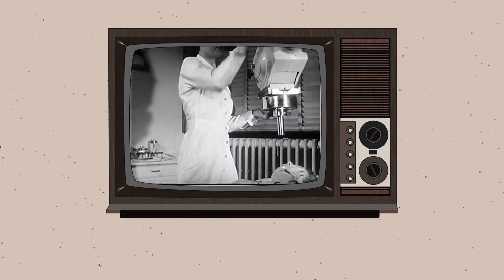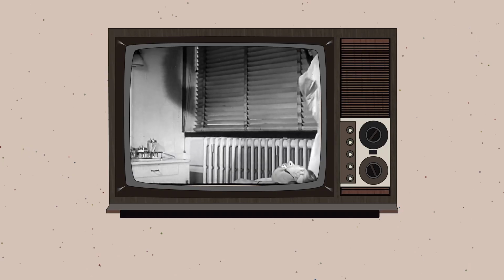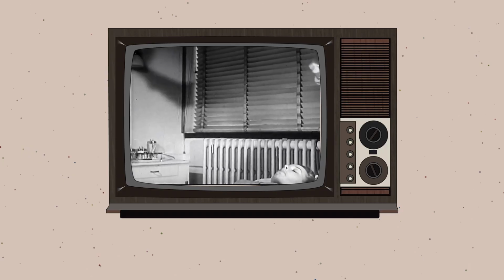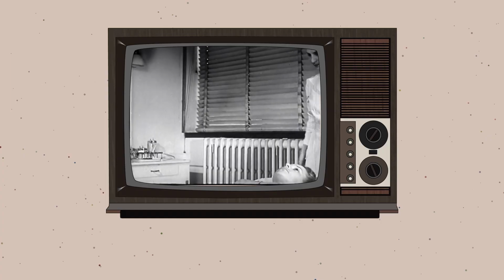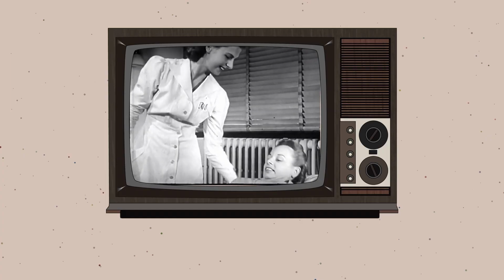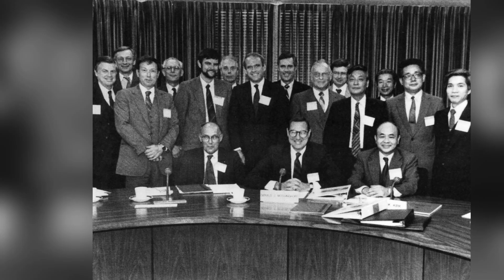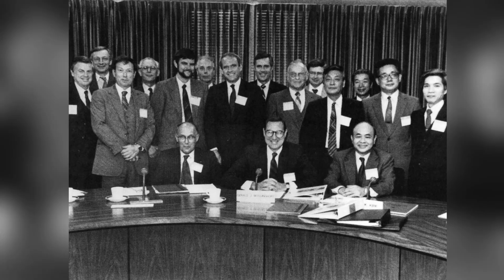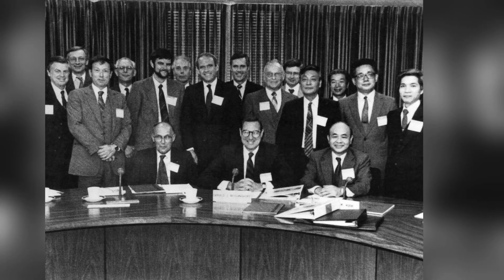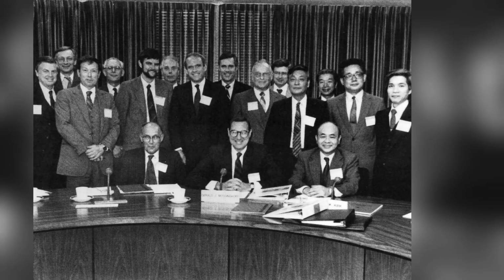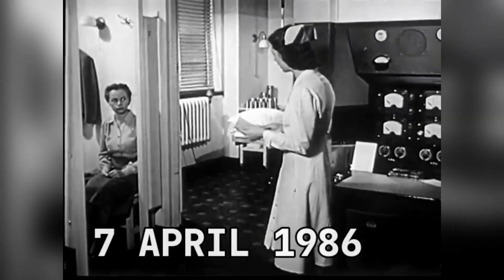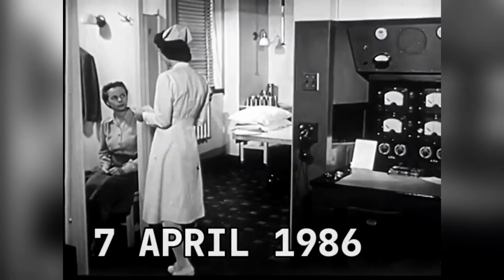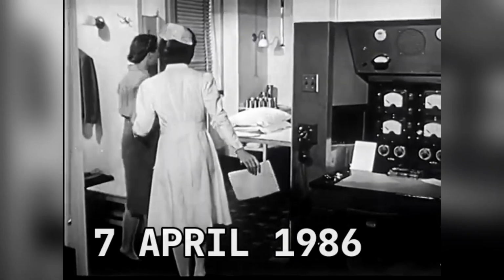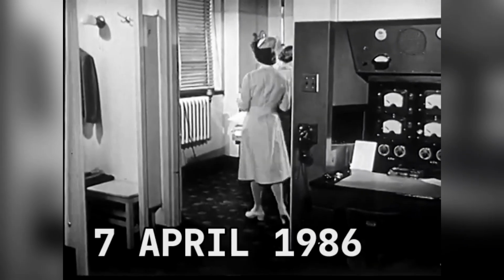March 21, 1986, Tyler, Texas. Malfunction 54 appeared twice, while the treatment room's video monitor sat unplugged and its audio monitor sat broken. Engineers tested for a day without reproducing the fault, and the engineer sent from head office reportedly explained that it was not possible for the Therac-25 to overdose a patient. Asked directly whether there had been other overexposures, AECL personnel said the company knew of none 7 months after Hamilton. That patient died of his injuries 5 months later. Back in service on April 7, 1986, the machine killed a second man 4 days after that.